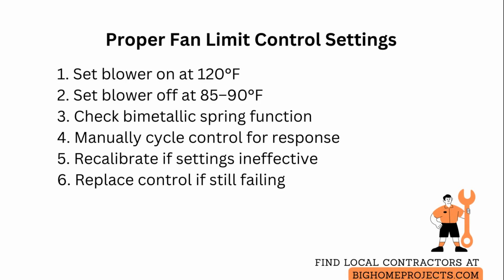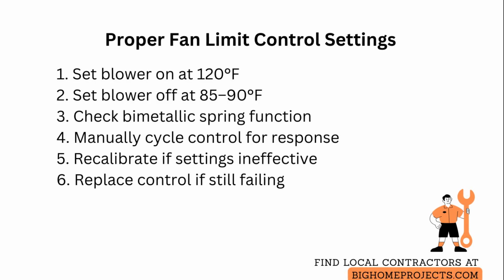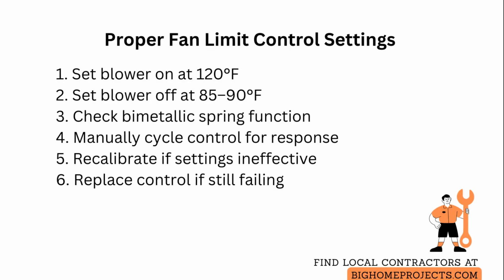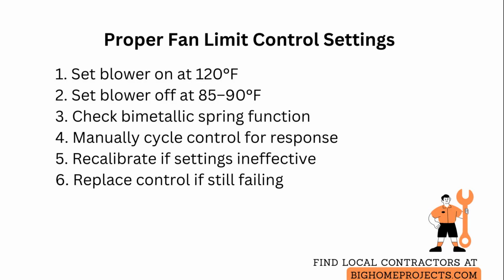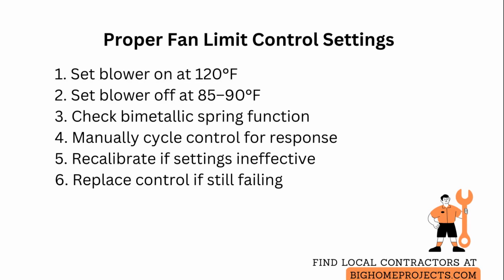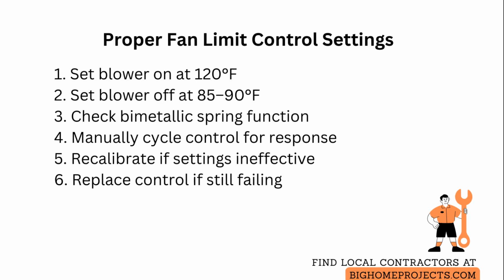When replacing, match the on and off differentials to the furnace rated heat rise so the blower does not pull cool combustion gases through the exchanger or leave heat stranded in the cabinet. Always power down the furnace and lock out the electrical supply before adjusting or swapping the control, and confirm power is restored and the burner cycles normally after work is complete.